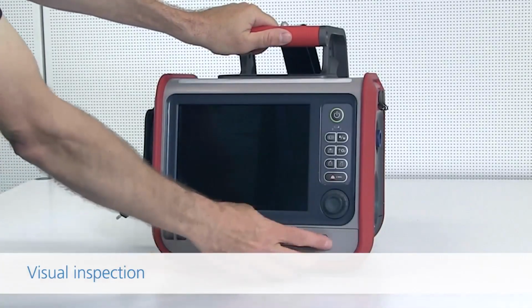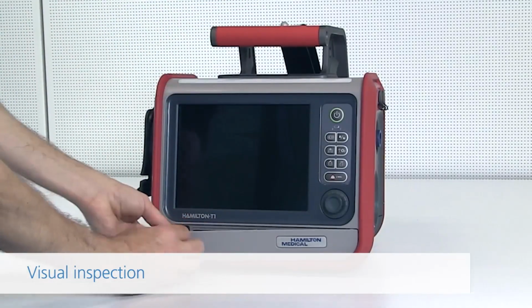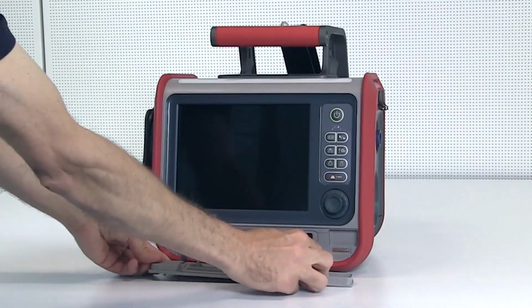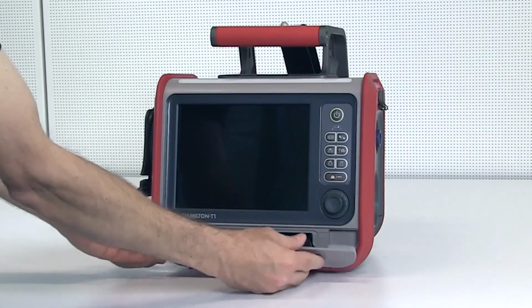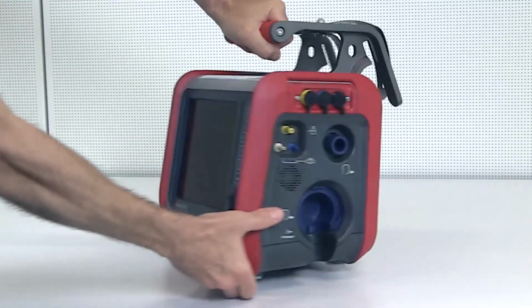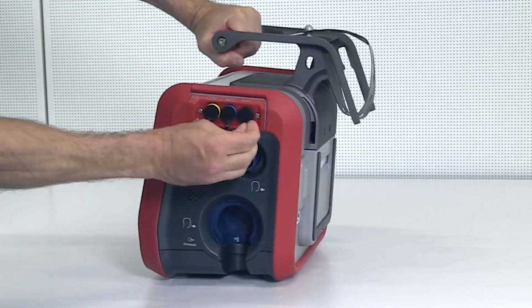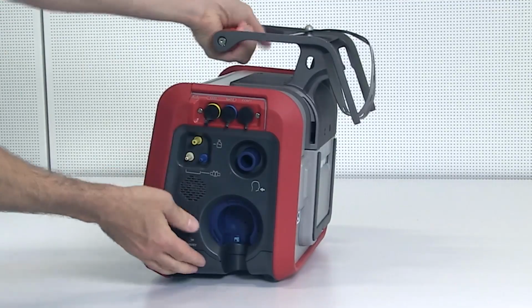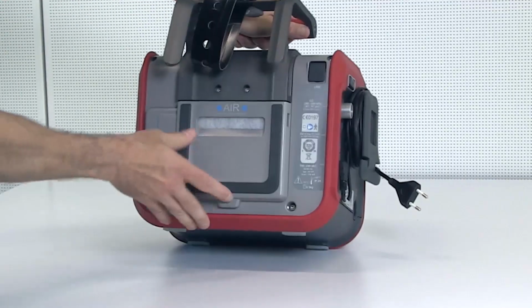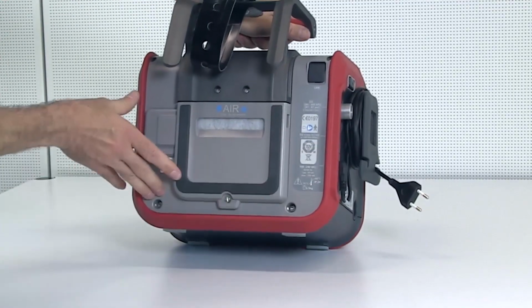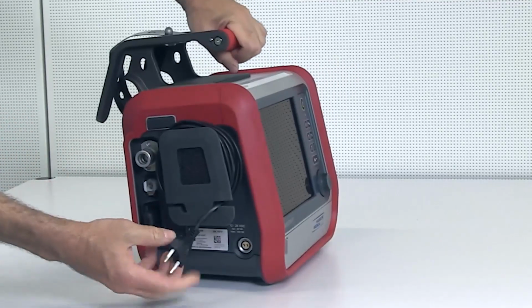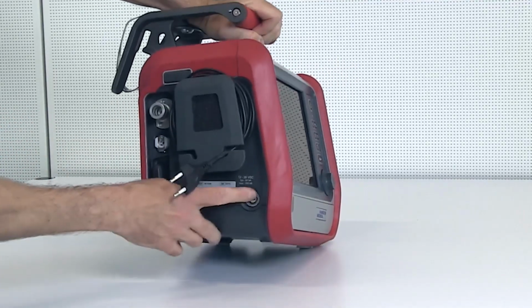Carry out a visual inspection of the ventilator unit. Inspect the ventilator unit and the power cord for damage or dirt. Make sure that all screws accessible from the outside, for example on the rear cover, filter cover, battery cap and option board, are tight. Check that all marks, symbols and labels related to safety are complete and legible.